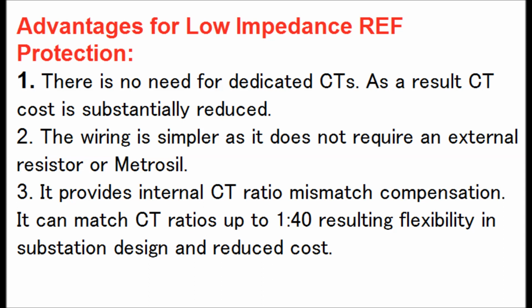Number 2 is the wiring is simple, as it does not require any external resistor and metrosil. Only the CT secondary inputs are taken into the relay. Number 3 is it provides internal CT ratio mismatch compensation. It can match the CT ratios up to 1:40, resulting in flexibility in substation design and reduced cost.